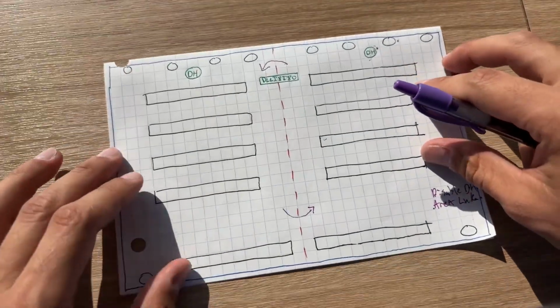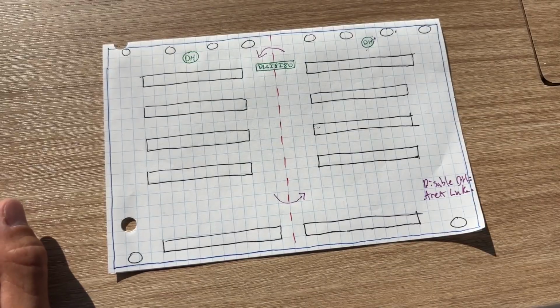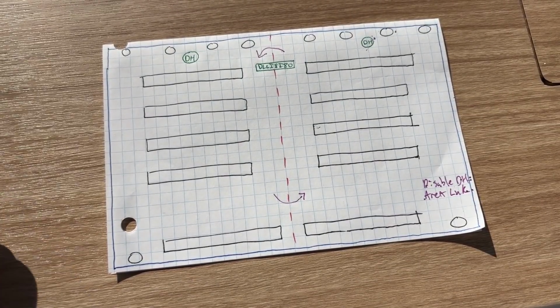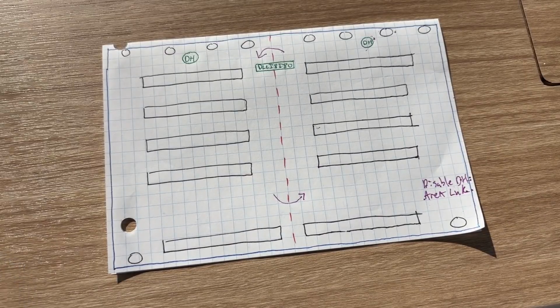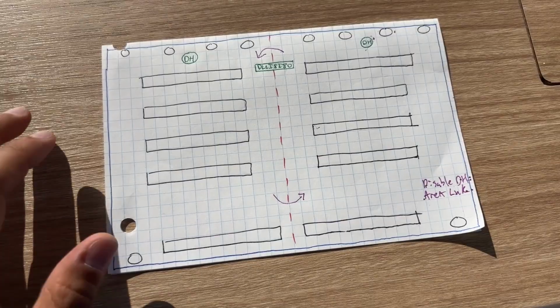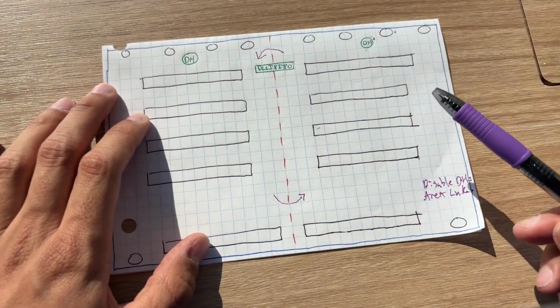So instead, I have option number 2, which works just as well. I have the same 2 separate areas drawn out. Each area has 4 logical channels of control. And during the day, each area has a sensor designated to regulate the 4 can lights by the window. When the partition opens, I link both areas together using area linking like this. This area gets linked to this one, this area gets linked to that one.